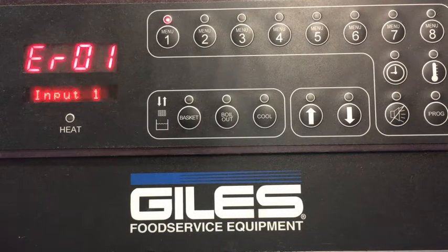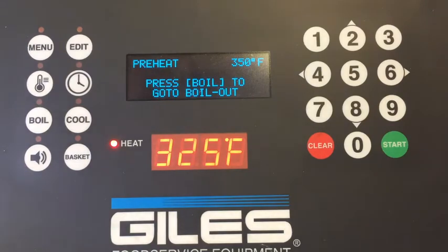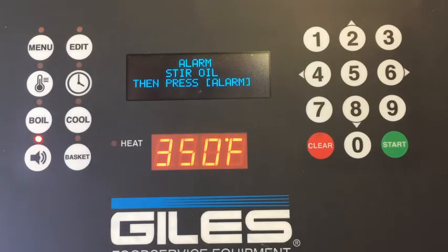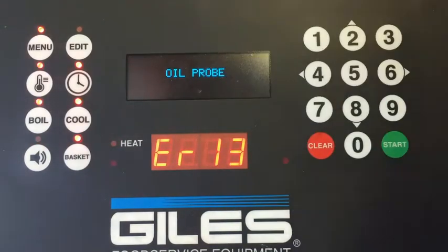So at that point, you just need to go ahead, shut it down, and try to find out where that probe is broke loose. Experience a problem with the variable probe, which is your main temperature probe. You could be going ahead and you're just heating and everything is just fine. Temperatures are slowly coming up. And then all of a sudden, you have a break in the line. Boom, it goes to oil probe error 13 and tells you that there's a problem with your main probe.